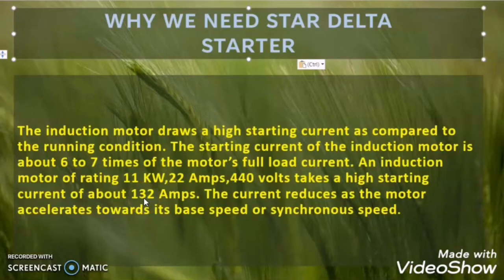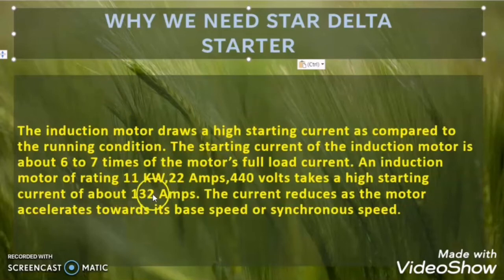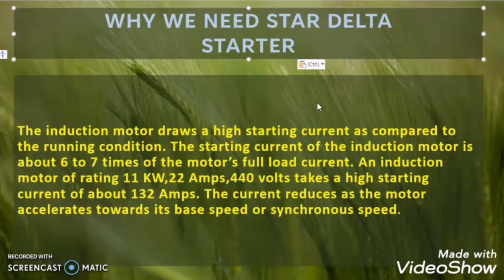Once we introduce the star delta technique, the motor will take only 3 to 4 times its full load current. So in this case, if the motor takes 3 times, the starting current reduces from 132A to 66A, which is comparatively very low. So the purpose of the star delta technique is to reduce the high inrush current which the induction motor draws at the time of starting.